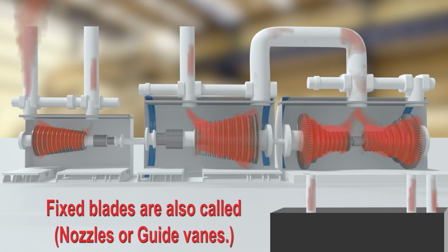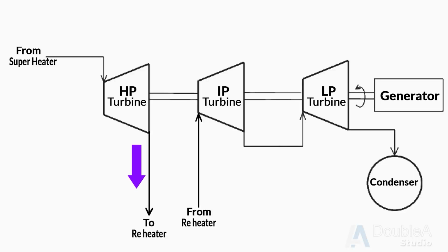As discussed earlier, the superheated steam goes to the HP turbine. Here it expands, loses its temperature and pressure. HP turbine exhaust steam is then sent to the reheater and reheated steam is sent to the IP turbine inlet. After expansion in the LP turbines, the steam pressure as well as temperature goes very low. Finally, this low energy steam is sent to the condenser for condensation. This condensate water is used as feed water.